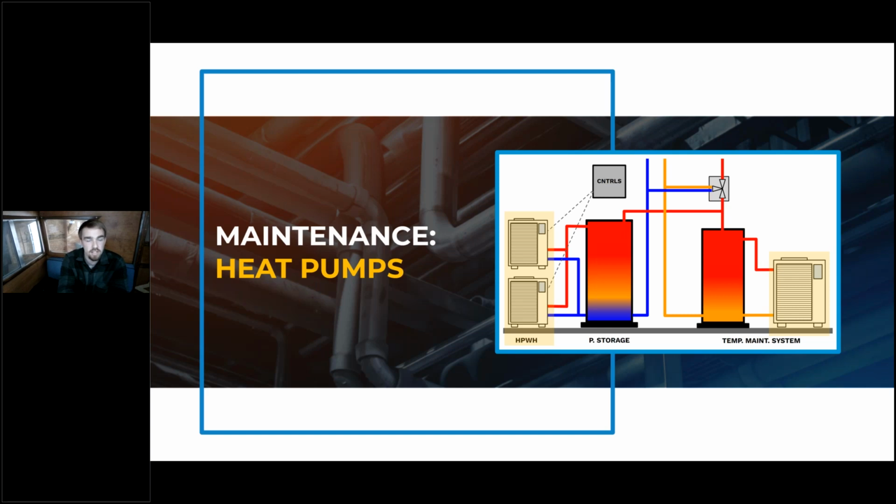There's often concern as well that a refrigeration technician might need to be involved in this maintenance. I can assure you on almost all heat pump water heating equipment, you don't actually need a refrigeration tech to maintain the equipment. There are repairs if a component fails and you need to repair down the road, that's where a refrigeration tech might get involved because they're breaking into this actual refrigerant system. But generally, all you're going to need is somebody that's comfortable working with mechanical or plumbing equipment to do some pretty basic tasks that usually would fall in the realm of just a building maintenance manager.